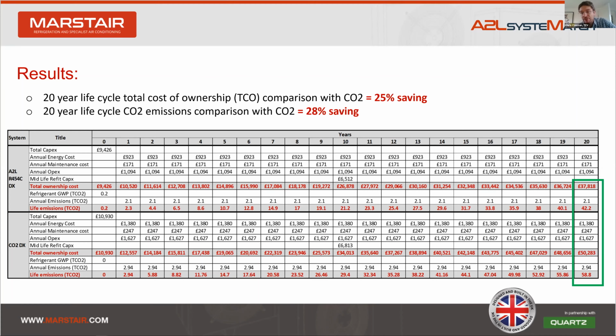During its 20-year life cycle, emission savings calculate to around 28%, which is a big change. So this, I believe, shows the real benefits that can be achieved through A2L refrigerants. Now, I'm not saying every refrigeration application should switch to A2L. That's not the case. CO2 and hydrocarbons all have their place in reducing the industry's refrigerant GWP, where we all need to meet our F-gas regulations.